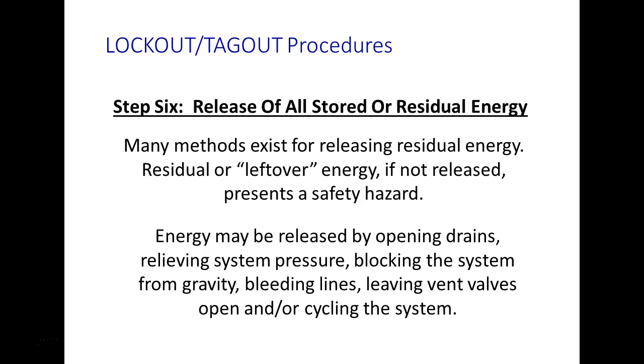Robots. A lot of times when you're working on these robots, you're in there working on the motor, those robots are up in the air, and you get in there, what could happen? They could fall. So blocking tackles, they have different methods that you can do that. So that would be stored mechanical energy. People forget about stored mechanical energy for some reason. You got something up in the air, and the mechanics is holding it up there, right? You understand? And then you go out and you kill whatever the drive is for that, and that thing can fall.